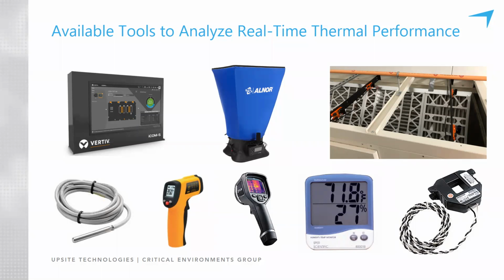I think Lars and I can tell you that we've been in so many data centers where you have a lot of perimeter AC units and you're looking at two next to one another, and one's heating, one's cooling, one's humidifying, one's dehumidifying. They're fighting one another, consuming lots of unnecessary energy, and it's not very efficient at all.